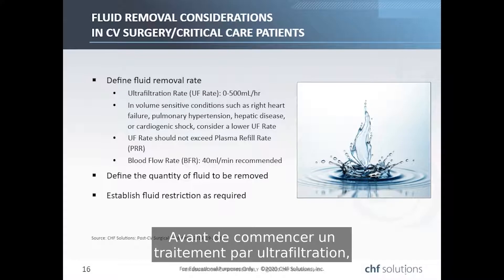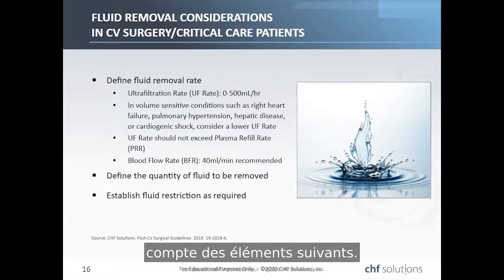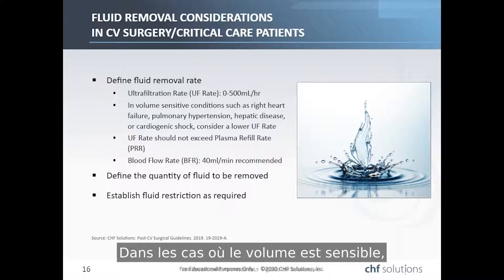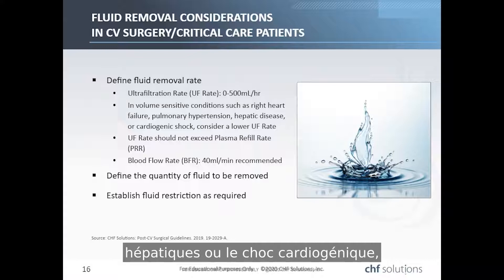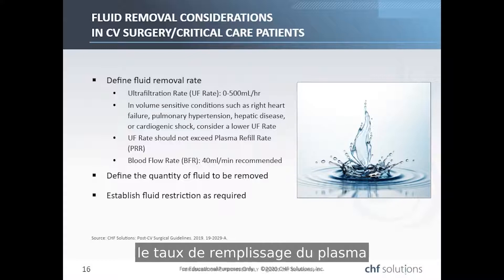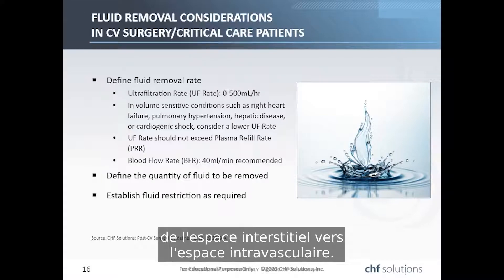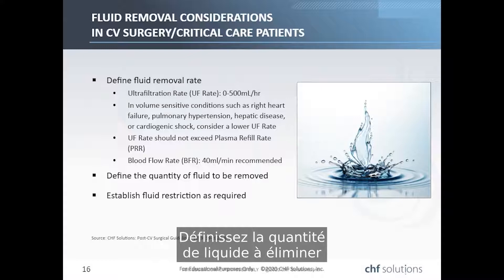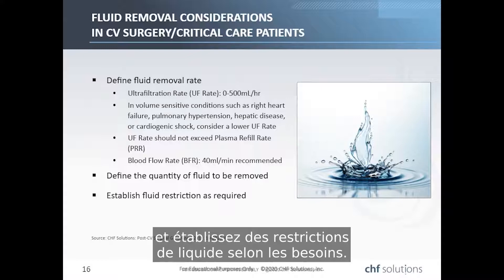Prior to initiating ultrafiltration therapy, prescribers should consider the following: define the fluid removal rate—the UF rate can be set from 0 to 500 mL per hour. In volume-sensitive conditions such as right heart failure, pulmonary hypertension, hepatic disease, or cardiogenic shock, consider a lower UF rate. The UF rate should not exceed the plasma refill rate. The recommended blood flow rate is 40 mL per minute. Define the quantity of fluid to be removed and establish fluid restrictions as required.